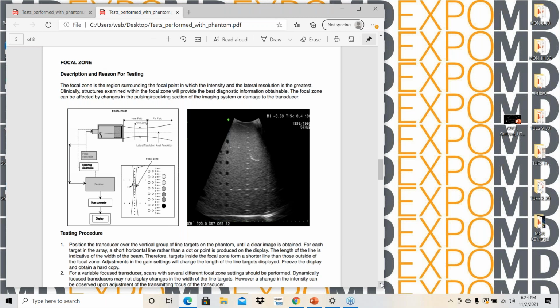You're going to use the approximation of what a cyst is. And those are the darker objects you can see there, the black ones. So you have those objects, and we're going to do this in just a minute, that you measure for depth. You don't measure these. About half my engineers were using those for depth measurements, and they were coming up with extraordinary numbers, right? And I'm like, how are you doing that? And so we had a class, we flew them all in for just kind of team building and stuff. And one of the points of the thing was I had my senior engineer do a phantom testing, record it, and then the junior engineer came in, did his measurements, and we compared them, and they were completely different. And so we solved it that day to show them how to do it correctly. So focal zones, important when you're looking at it.